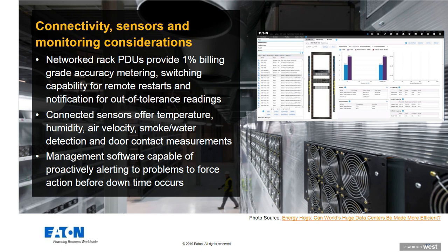Modern PDUs are continually logging over 100 data points per PDU. That may seem like a lot, but when you account for all the outlets, voltage, current, and power, all of this data is being logged by the PDU. That information is used to generate alerts, so you could get an alarm telling you there's an overcurrent on an outlet section, which would immediately tell you there's a problem.